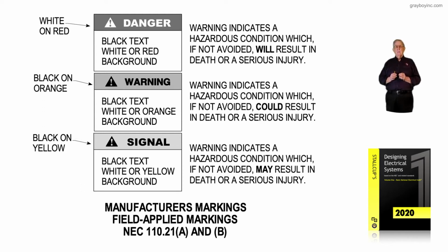Now to the right of the equipment there, you see other labeling review sections. If a high leg was involved, we would look at 110.15, and that gives you the high leg requirement. It has to be orange or some kind of identification that would please the authority having jurisdiction. 230.56 gives the listing if it's service equipment.